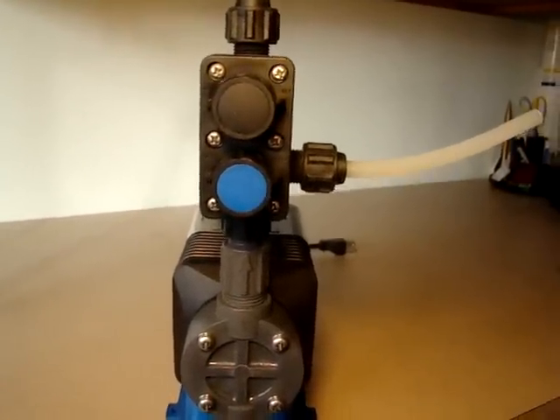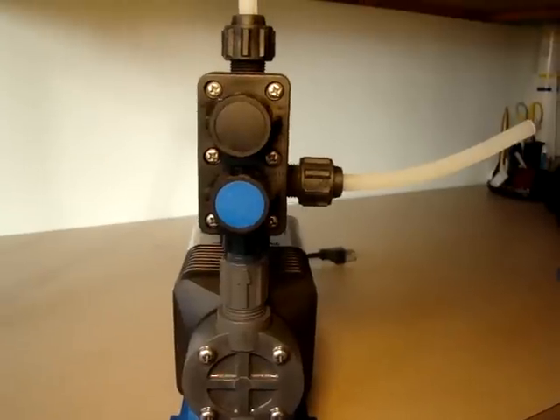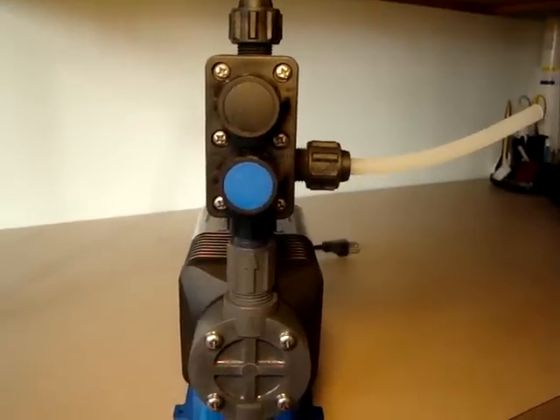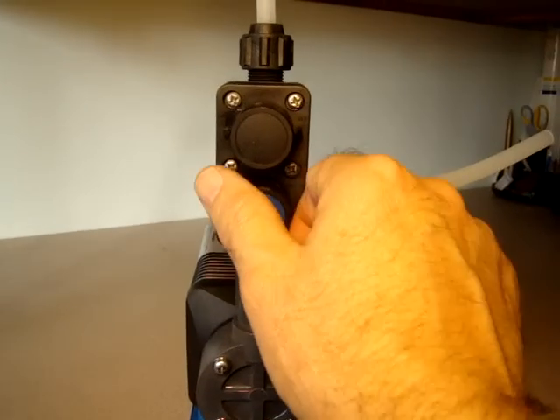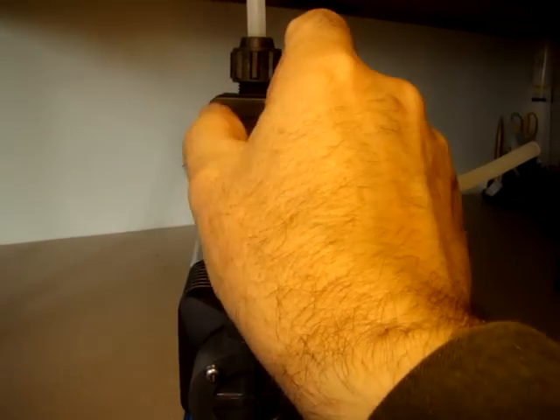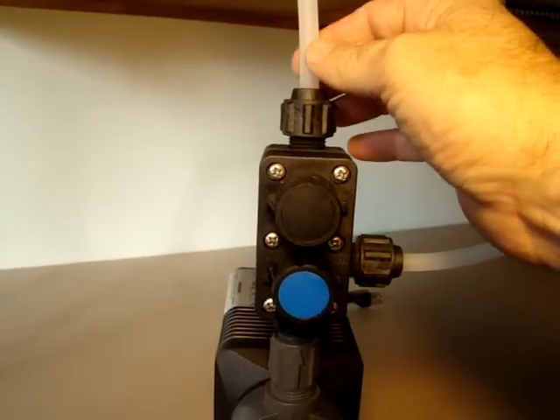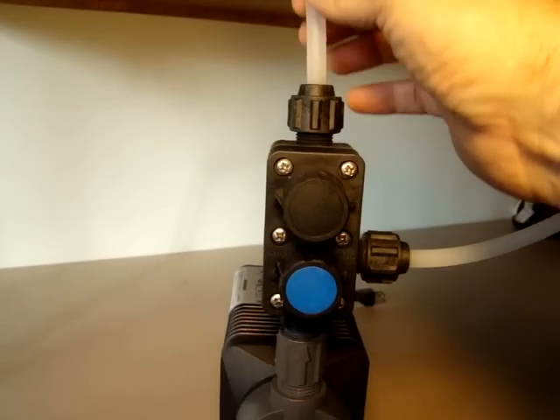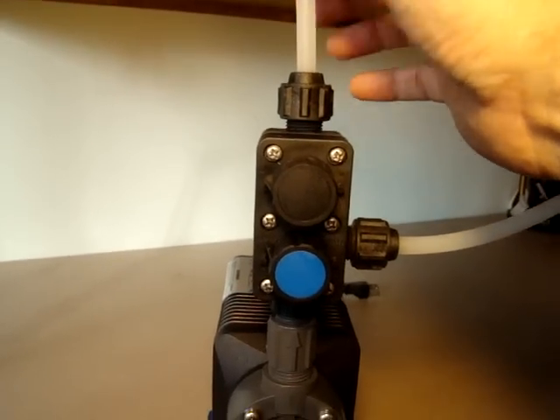You want to continue that purging of the air until you don't see any more air. Then all you will need to do is to turn these knobs back, and making sure the pump is running again, you need to check up here to see if you can feel any pulse.